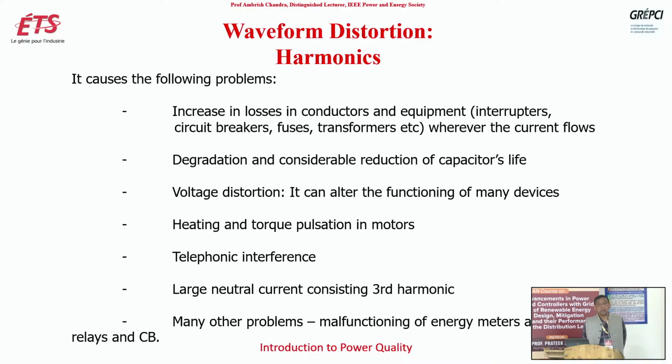the fundamental frequency is generating a rotating magnetic field in the air gap between stator and rotor, and a stable torque is produced and the rotor rotates in the same direction as the rotating magnetic field. And then we have, suppose, voltage distortion at the terminal, then the fifth harmonic may be there, sixth, seventh harmonic currents may flow in the motor. Then the fifth harmonic, as we will see today also, and why the fifth harmonic is a negative sequence harmonic and the seventh harmonic is a positive sequence harmonic, we will see that today.